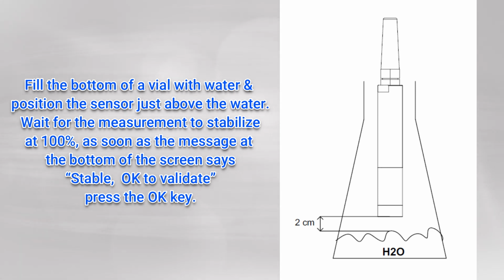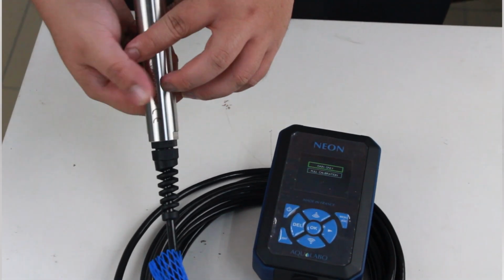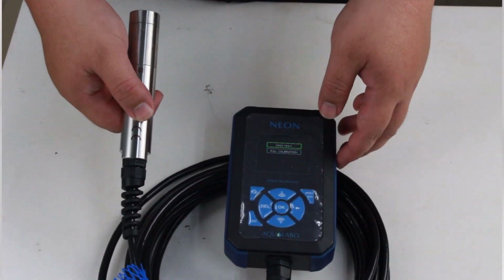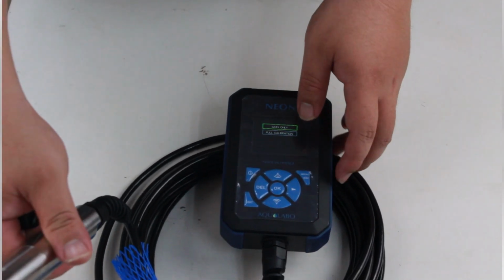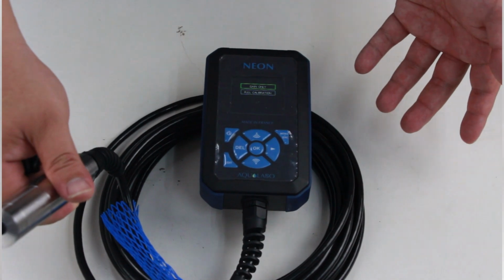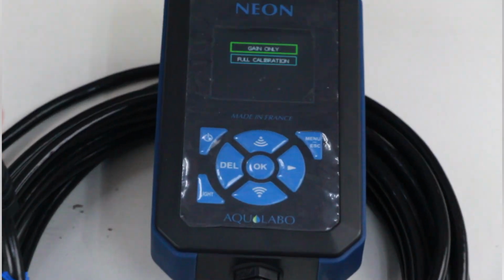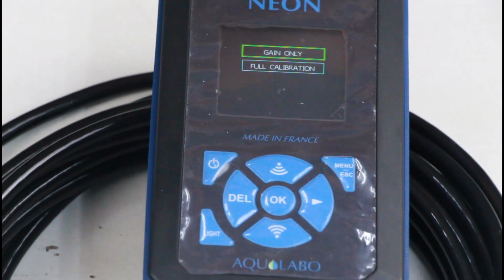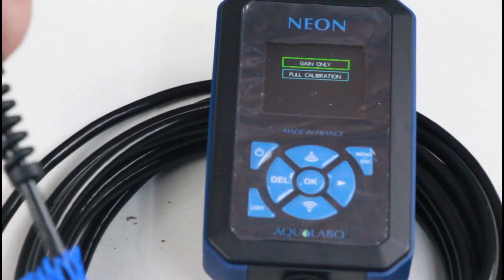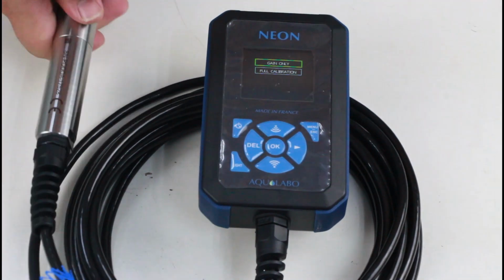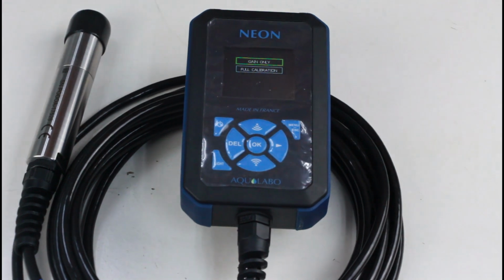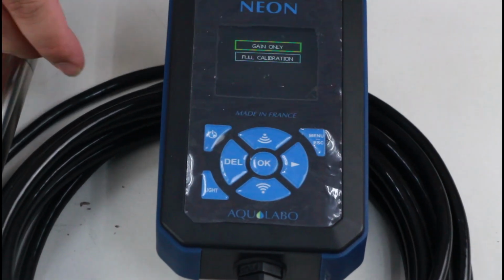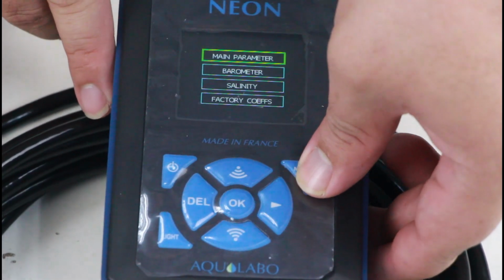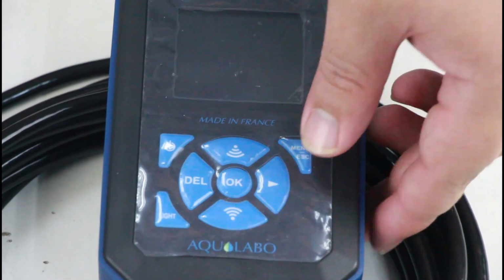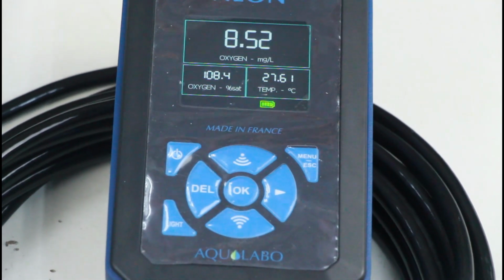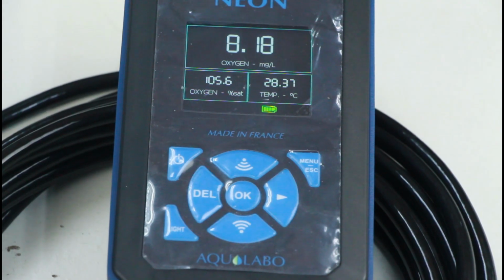Then show it beside here. We just follow the procedure. Then after that, press gain only again. After that, the unit will run and show stable. Once stable, press OK to validate. That's all. As for the full calibration, we recommend to send this unit back to us for running the full calibration. The frequency for this calibration, we recommend once a year.